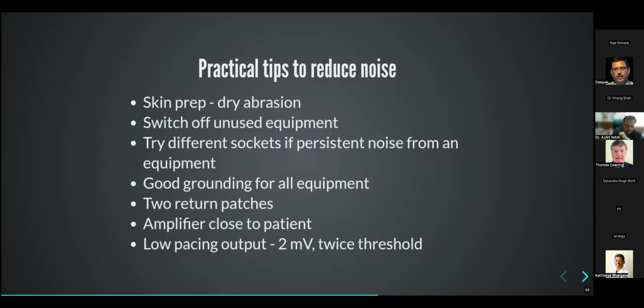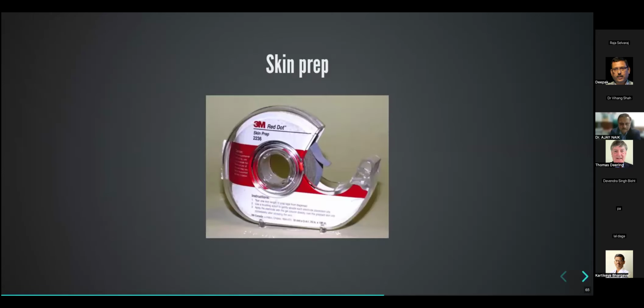And also remember that when you're recording unipolar signals, you're often using Wilson central terminal as a reference. So clean ECGs are essential to record clean unipolar electrograms. Skin preparation with dry abrasion is good to do. Any unused equipment should be switched off. Sometimes, like I said, sockets may be leaking. Good grounding is important. Two return patches for the patient help. Keep the amplifier close to the patient. Pacing outputs, keep them close to threshold, because they introduce saturation and noise when you're pacing.